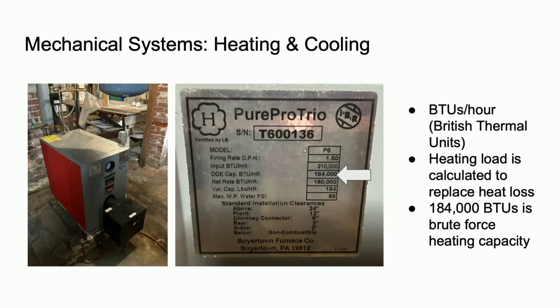So for this case, it's tiny on my screen, but it's 184,000 BTUs. That is a tremendous amount of heating power, just brute force heating. If you have an old uninsulated house, 184,000 BTUs will do it. But then if you go through and insulate the house and make it a lot tighter, then 184,000 BTUs is ridiculous, way too much power.